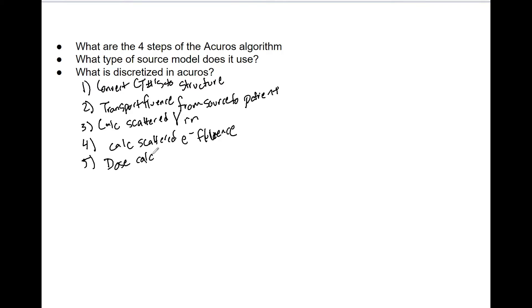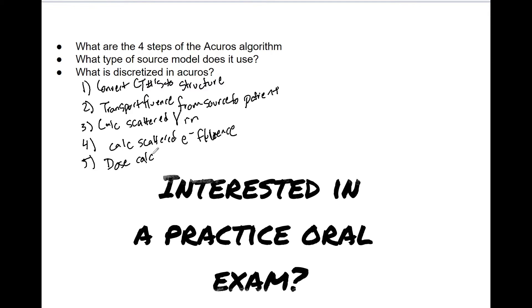So remember that ACUROS is four or three or four times faster than AAA because steps two to five are done once per global calc. So that makes it much faster, especially in those instances like SBRT lungs or where there's a lot of heterogeneity. ACUROS is much faster and proven to be more accurate than AAA as well.